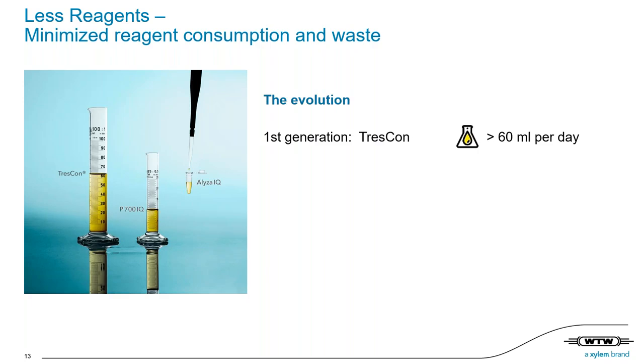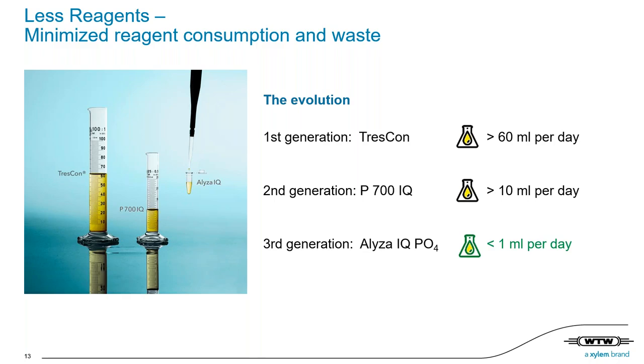Released in 1999, so exactly 20 years ago, the TresCon platform was a state-of-the-art technology with a pioneering modularity. The reagent consumption was more than 60 milliliters per day. The next generation, the P700 IQ, released in 2013, already had a significant decrease down to 12 milliliters per day. Alyza IQ now, 20 years after the release of TresCon, finally reduces the reagent consumptions again significantly, resulting in 0.75 milliliters reagent per day. This also results in a dramatic decrease in chemical-containing liquid waste. I'll come to that now.